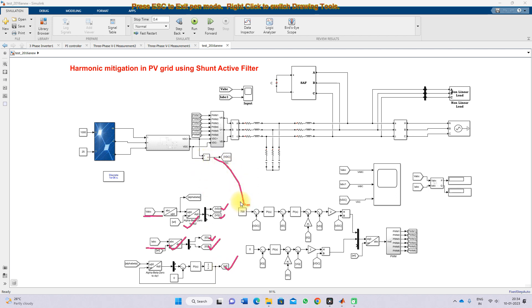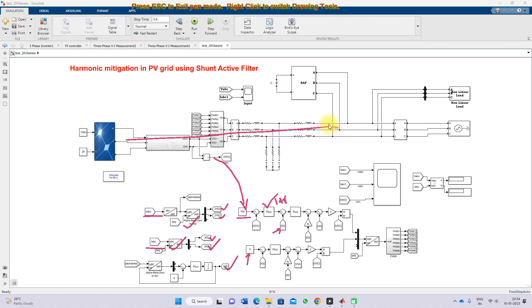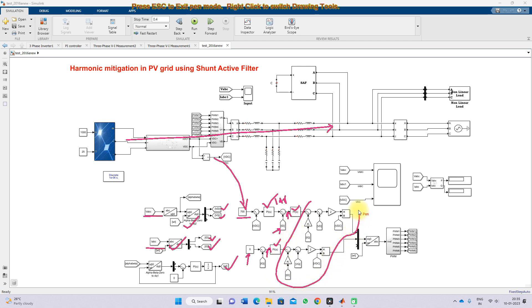Here we measure the DC link voltage, compare it with the reference voltage, and process it via a PI controller. This controller generates the ID reference current. The ID reference is compared with the actual ID of the PV inverter. The IQ reference is set to zero because we are sending only real power to the point of common coupling via this inverter from the PV source. The IQ reference is compared with the actual IQ, producing an error current, which is processed via PI controllers. This portion is known as the feedforward decoupling control concept.